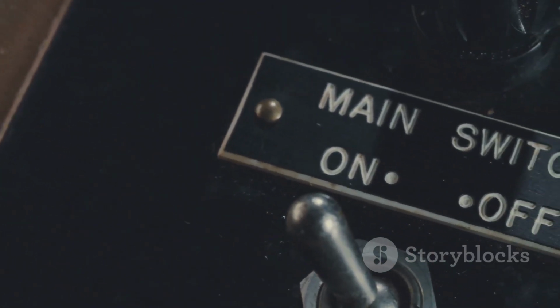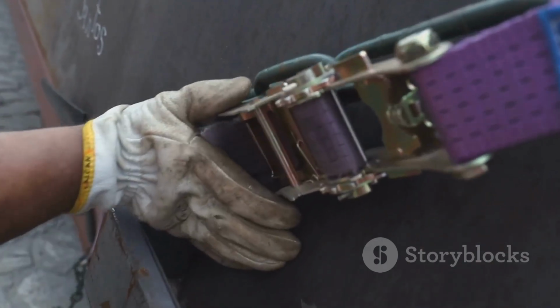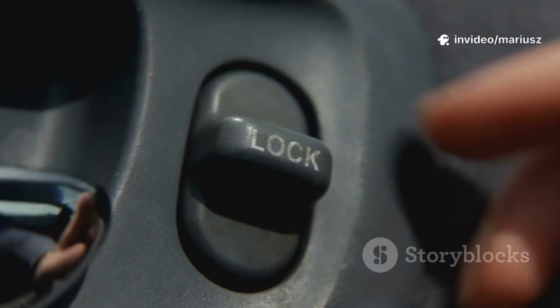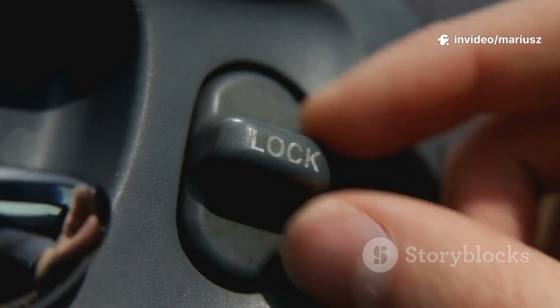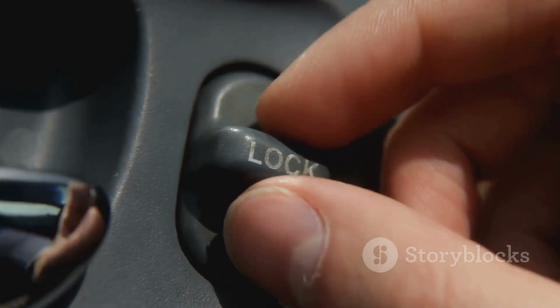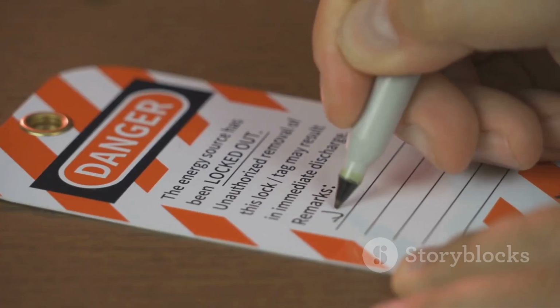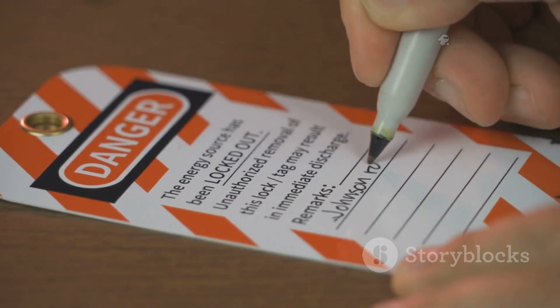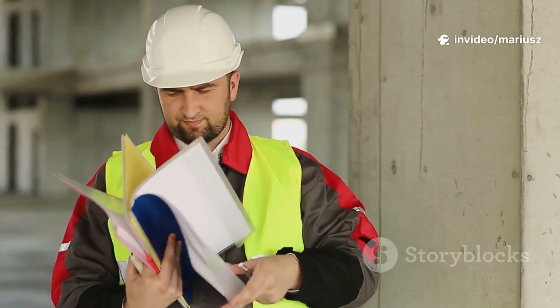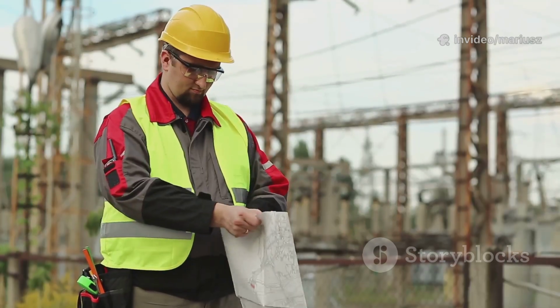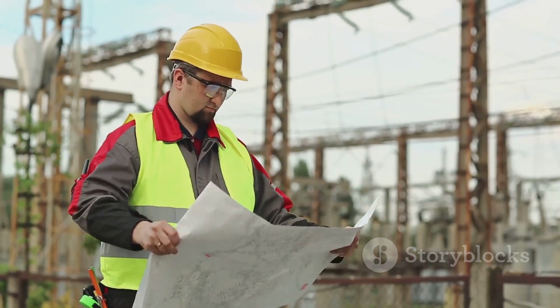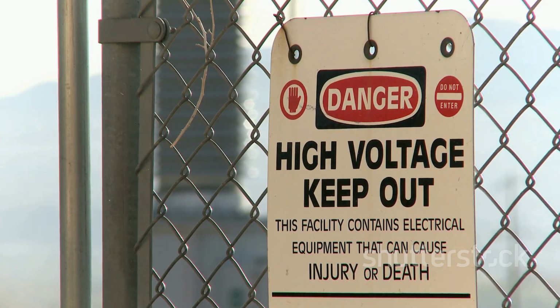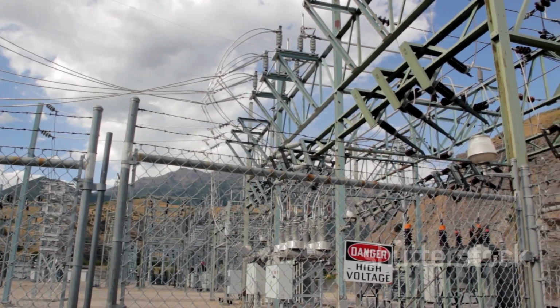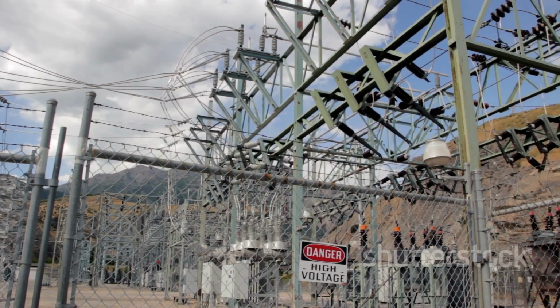The third stage is to lock off and post notices. After an isolation is performed, it must be secured. The authorized person applies a personal safety lock to the isolating device, the switch, the valve handle, and so on, to prevent it from being operated. A caution, do not operate notice is attached directly to the lock. Then, a main notice, the safety document, is posted at the point of work itself. This document clearly states what is being worked on and what safety measures are in place. This combination of locks and notices provides both a physical barrier and a clear visual warning system, ensuring everyone in the vicinity understands that the equipment is under a formal safety procedure and must not be touched.